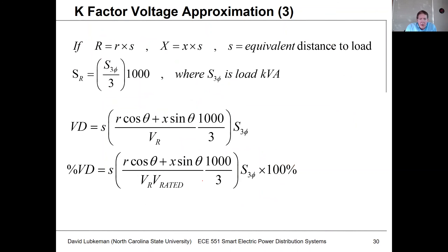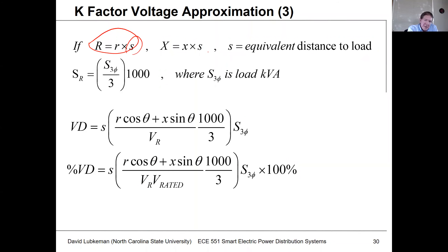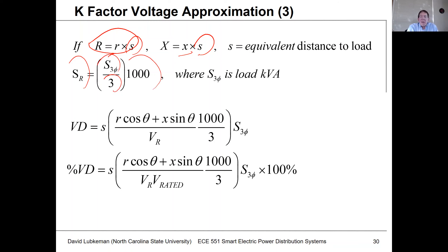We calculate R as a function of the equivalent line length S, where small r and small x are the equivalent resistance and reactance per unit length — usually per mile or per kilometer. For Sr, the single-phase load, we take the three-phase load, divide by three, and multiply by 1,000 if we want S3-phase to have units of KVA. That's typically a good number for distribution-level calculations.